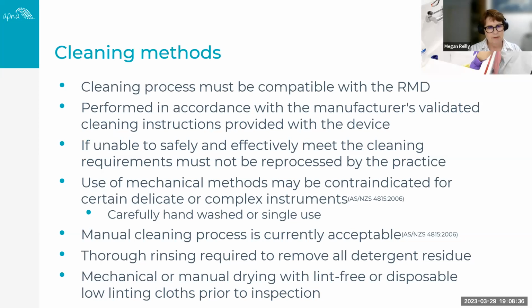In relation to our cleaning methods, the cleaning process must be compatible with the RMD. So we're now starting to transition to a process that when we purchase our reusable medical devices, we ensure that we've got the manufacturer's instructions, and they will provide validated instructions on how you reprocess that item. So you do that in accordance with those instructions, and in particular the cleaning instructions. If you're unable to safely and effectively meet those cleaning requirements, then you shouldn't be reprocessing within the practice, and the standard's pretty clear on that.